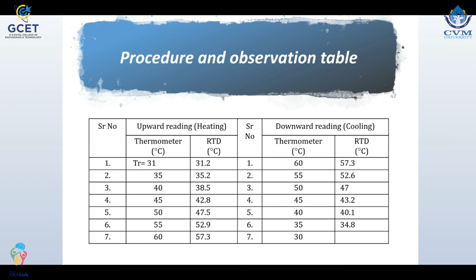In a similar way, we have taken the remaining readings in increasing order of temperature and decreasing order of temperature with respect to time. So now, as per our observation table, we can conclude that the error present in our RTD is approximately minus 2.5 degrees Celsius. This is how we can perform the calibration of our resistance temperature detector.